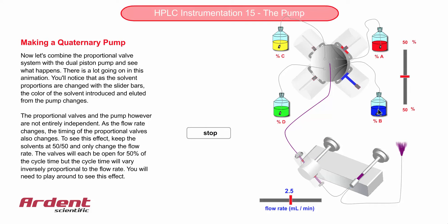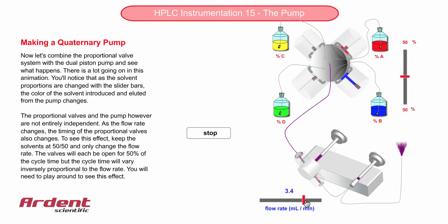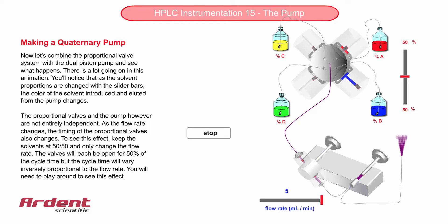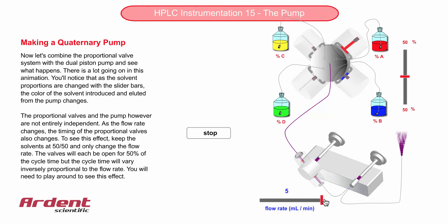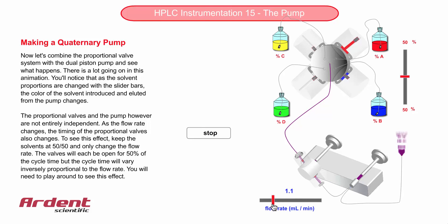You'll notice that the solvent colour eluting from the pump remains purple, but although each of the valves will still be open for 50% of the time, the valves open and close more frequently at higher flow rates. Have fun with this but make sure you understand exactly what's going on before moving on to the next page.